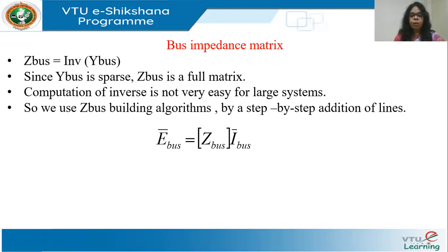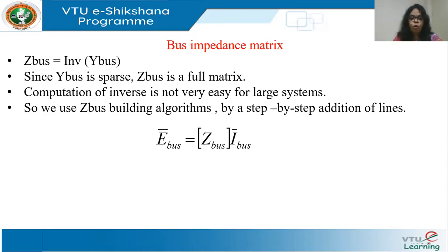The equation we will be using is this, called the impedance reference frame of representation. Here, E_bus (or V_bus) is equal to Z_bus times I_bus. E_bus is the vector of bus voltages, Z_bus is the bus impedance matrix, and I_bus is the vector of current injections at various nodes. E_bus will be an N×1 vector, Z_bus will be an N×N matrix, and I_bus will be an N×1 vector.